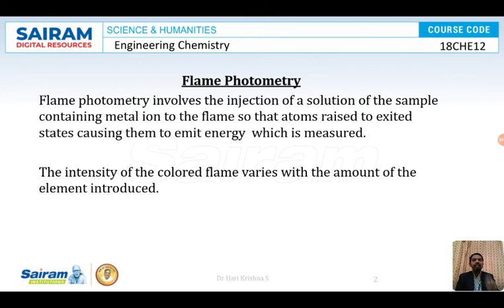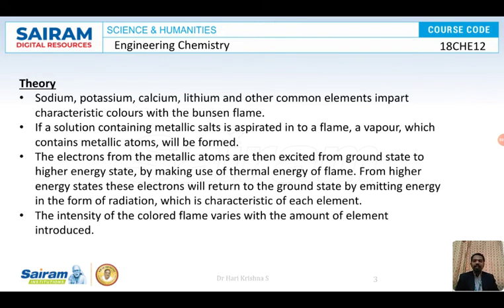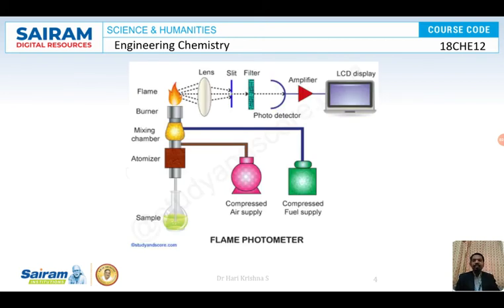Any metal, when excited to a high energy level and coming back to ground state, if it gives a color that falls in the visible region, only that type of element can be estimated using a flame photometer. A flame photometer contains a compressed air supply and a compressed fuel supply. If you want to estimate sodium chloride, you take a sodium chloride solution of known concentration and dip a capillary in it.